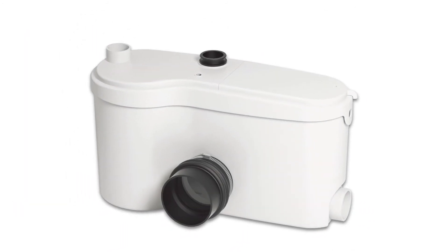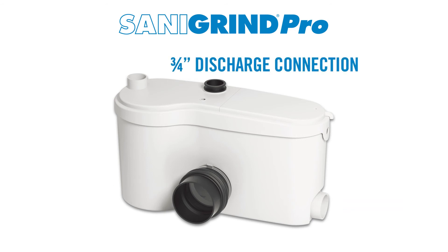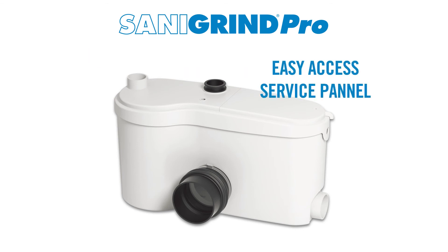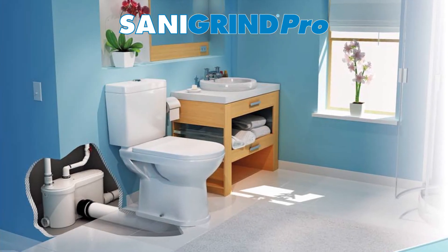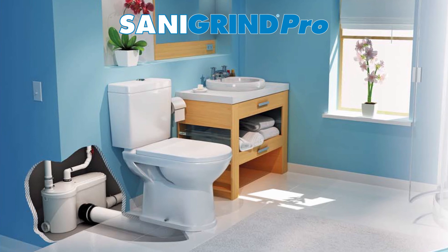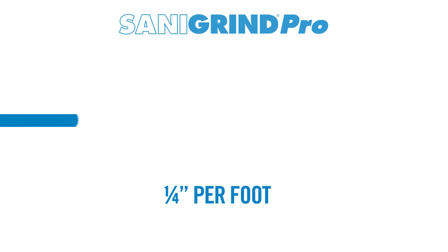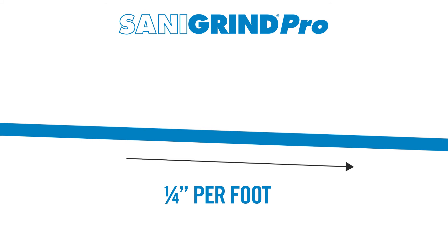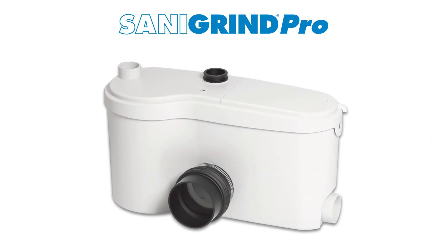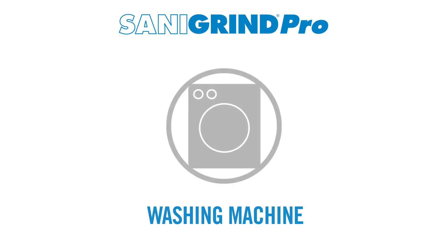Another alternative grinder unit is the SaniGrind Pro. It has two 2-inch inlets, a 3/4-inch discharge pipe, a 1.5-inch vent, and an easy access service panel. It is made for commercial applications and is specifically designed to connect to any conventional toilet with a bottom outlet — no need to use a specific rear discharge toilet. Note that there should be a minimum one-quarter inch per foot gravity fall on the waste pipe coming from the toilet into the pump. The SaniGrind Pro will discharge grey water from a variety of fixtures such as sink, bathtub, shower, urinal, and even a washing machine with an indirect connection.